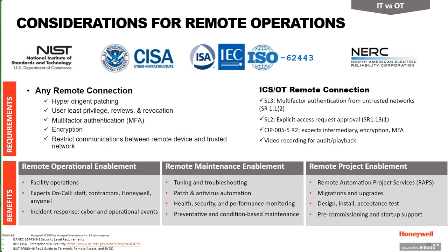With OT remote connection, you need to not just give a blank check like a VPN to these systems. You need to really control when someone is accessing it, control it from your facility, so that just because I have a username and password doesn't mean I can log in at any time, because I have my plant, my lab, my equipment running. At your plant, you need to give authorization on a session-by-session basis. You need to be able to record it and do playback for audits or for any reason whatsoever. You should be able to do video recording for audit and playback.